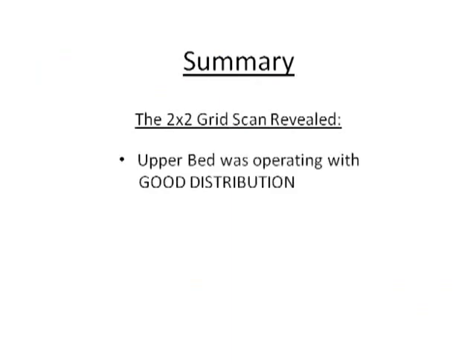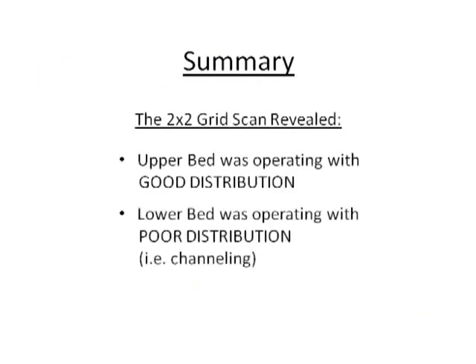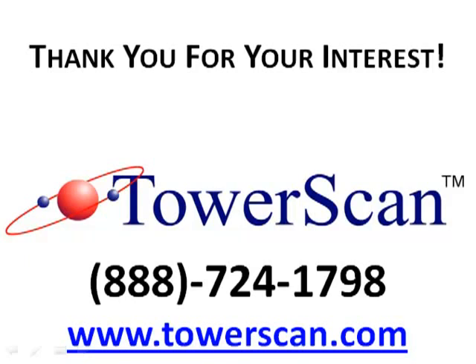In summary, the grid scan revealed that the upper bed was operating with good distribution, but the lower bed had poor distribution, maldistribution, channeling, whatever you'd like to call it. Thank you for your interest in TowerScan.